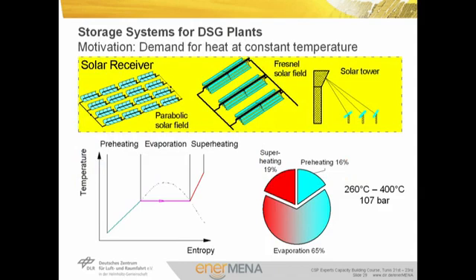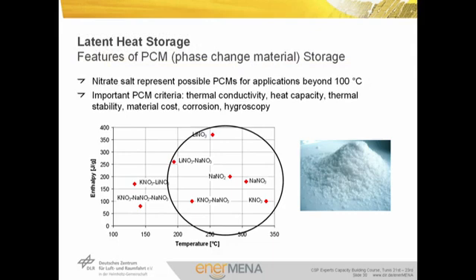The motivation for the development of latent heat storage systems is a demand for a storage system able to store energy at a constant temperature. If water is used as heat transfer fluid in the absorbers, a large fraction of the energy is transferred at constant temperature during the evaporation process. The storage system must then be able to store energy at constant temperature during the condensation process. In a typical direct steam generation process, about 65% of the energy is transferred by wet steam during condensation or evaporation, and the storage system must be able to store this energy at a constant temperature.